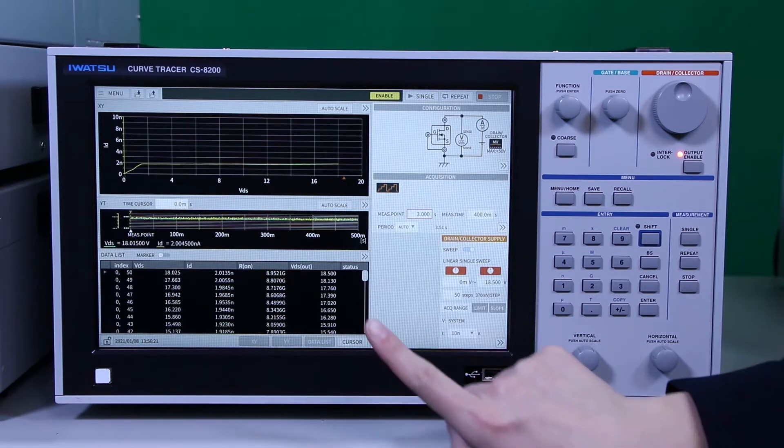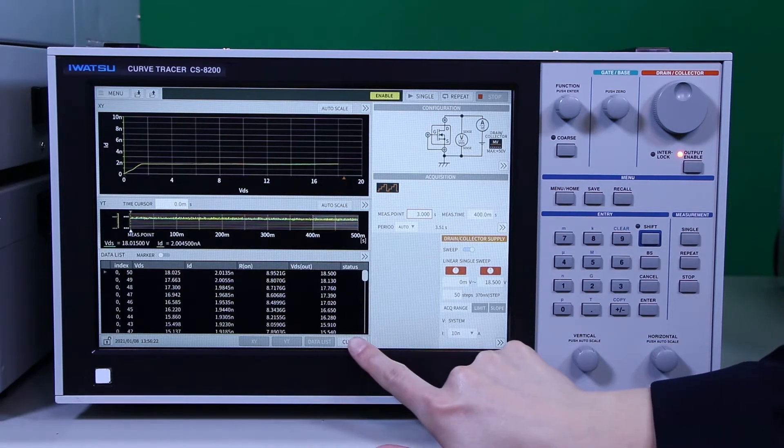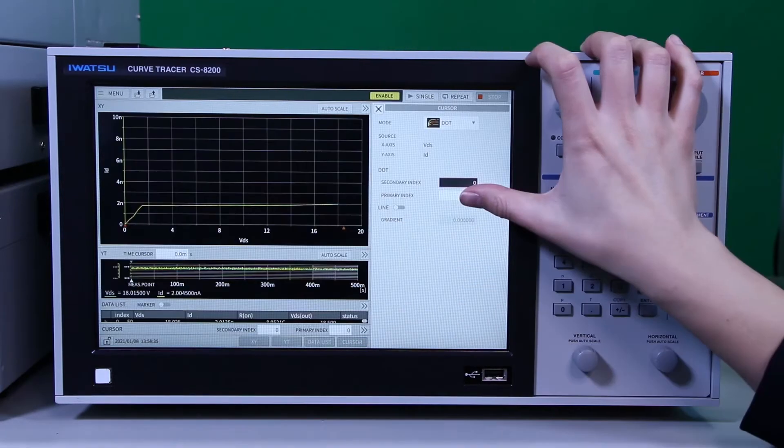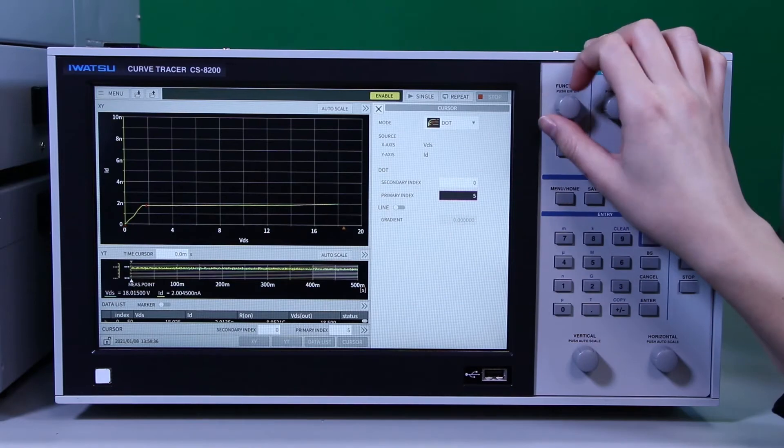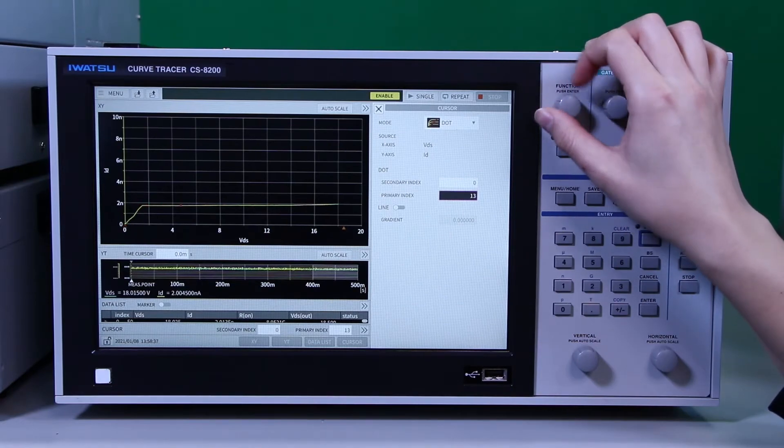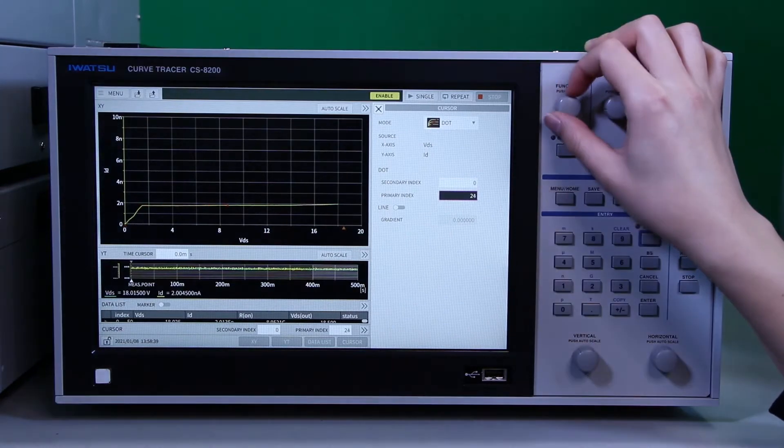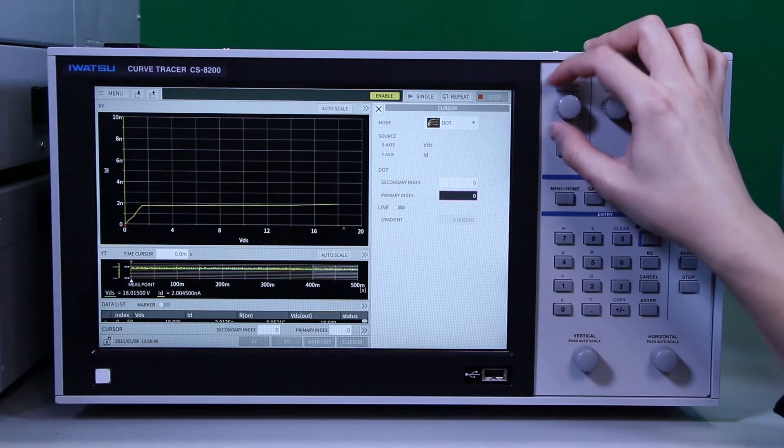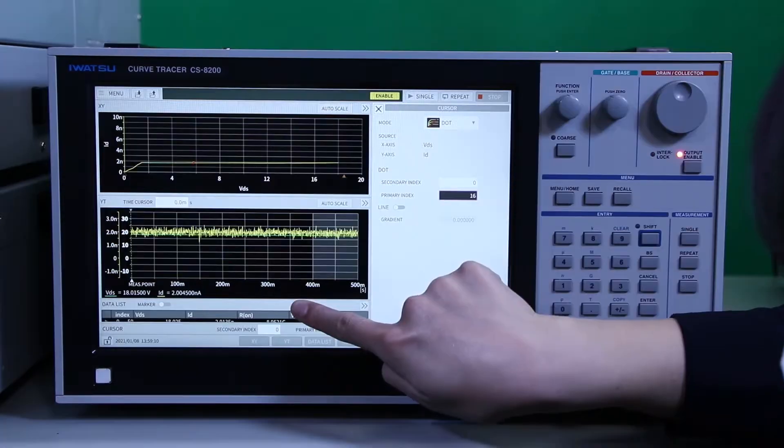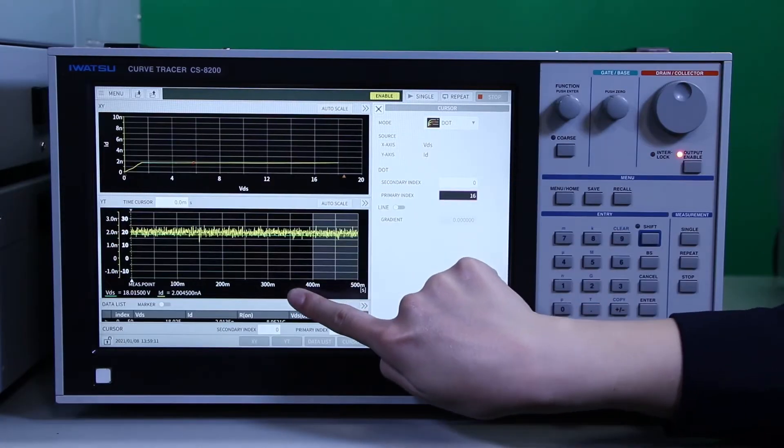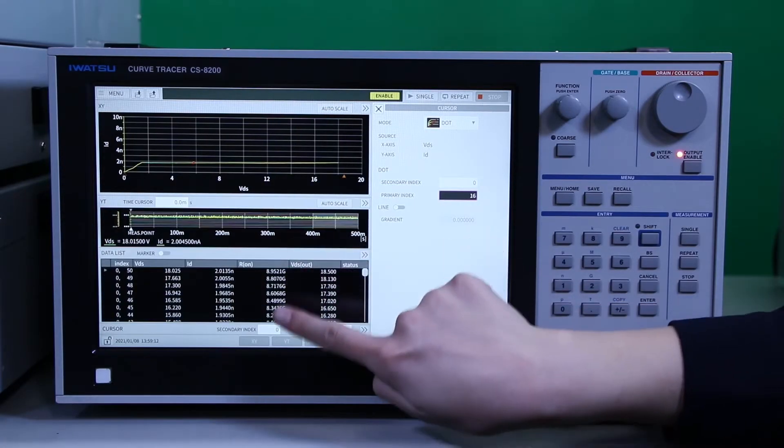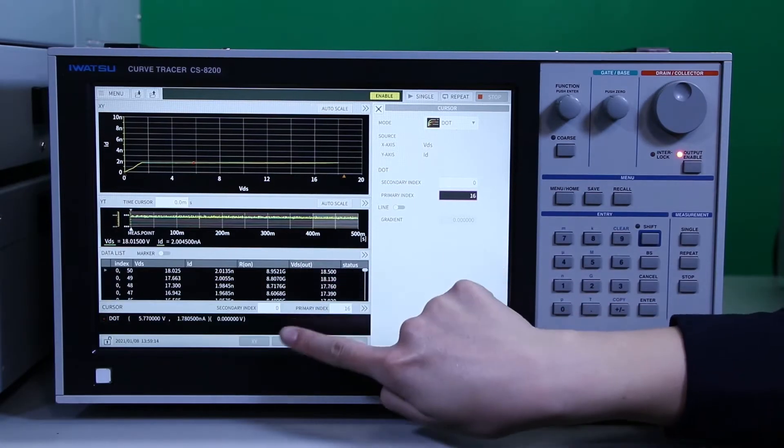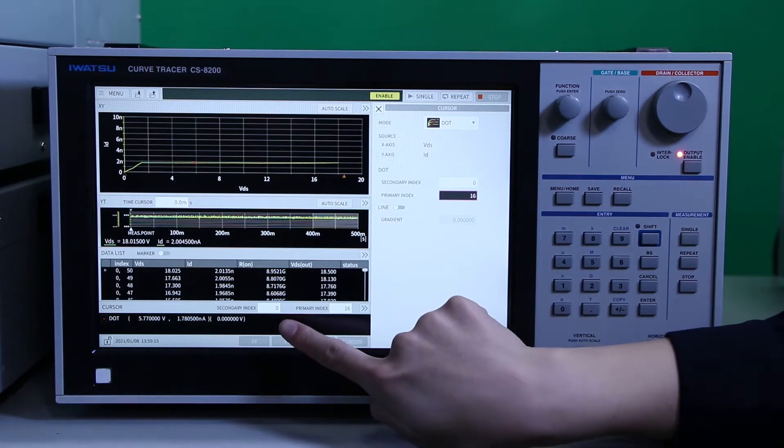CS8000 can show not only IV curve but also VV curve and II curve. Previous model, CS3000 series, required you to use software to show VV and II curves. But the CS8000, you don't need it.